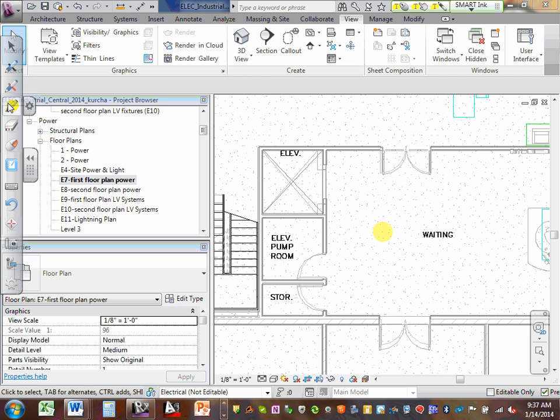So you have to control the elevator via smoke detection. Smoke detection, of course, is a part of the fire alarm system. Here's your elevator here. Here's your elevator equipment room. Some things that absolutely have to be there. Number one, you have to have a smoke detector in the elevator lobby. Okay? And why? Because if we get smoke in this elevator lobby, we need to recall the elevator somewhere else.